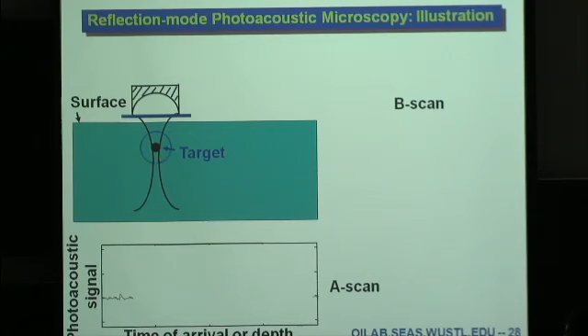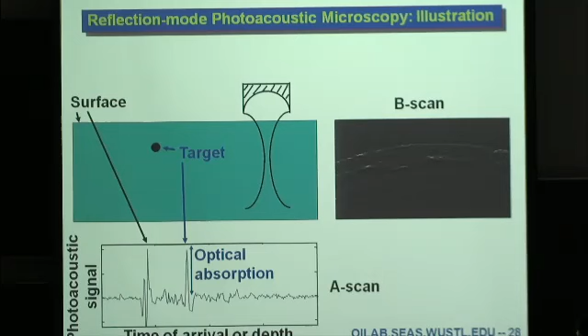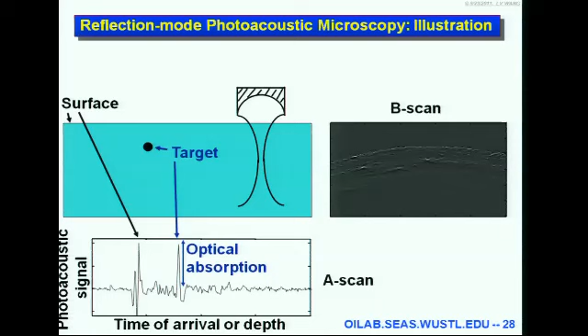And you get this time trace. This target becomes a spike right here. Well, you can imagine if you have a second target somewhere deeper, you would have a later arriving spike. We do Hilbert transformation of this time trace to form an envelope for envelope detection, and that will give you a one-dimensional image called an A-scan. It's a depth resolved image because we can convert time into depth as we know the speed of sound very well in soft tissue. If you scan across this tissue, you form a two-dimensional B-scan image. If you raster scan on the surface, you get a 3D image.